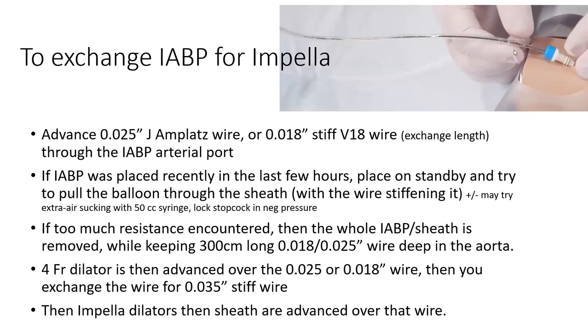So if it hasn't been inflating for several days, the balloon pump may still have a low enough profile when deflated that you can pull it through the sheath. But don't pull too hard. Try to pull it along with the support of the wire. It comes out through the sheath, great.